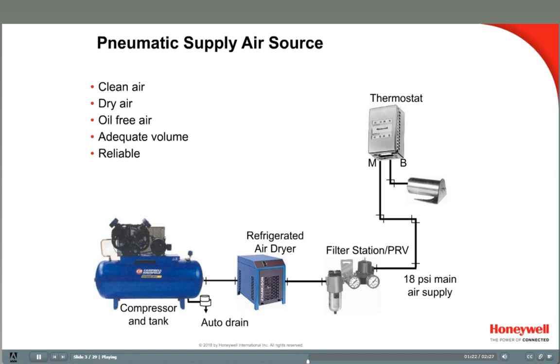After passing through the filter, the air enters the pressure-reducing valve. This limits the outlet pressure to typically between 18 and 25 psi, depending on the system. Some systems use a pressure-reducing valve that can be set to deliver one of two pre-set pressures — usually 13 or 18 psi for Honeywell equipment, but other manufacturers use pressures between 15 and 25 psi. The switchover from one pressure to the other may be triggered by a time clock, often used for temperature setback in a day-night system.